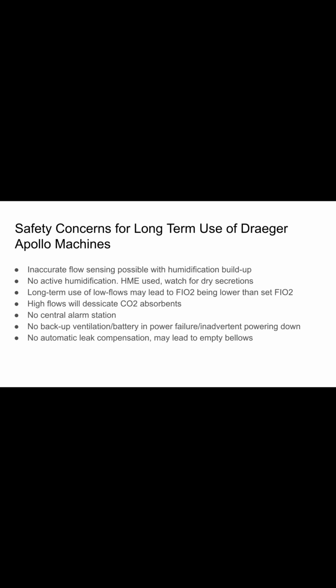So now that you've seen the basic setup for our machines, I want to talk a little bit about the safety concerns for using these anesthesia machines as ICU ventilators. Problems we anticipate have to do with humidification buildup inside the machine itself. Because these are going to be used for longer periods of time, the likelihood is that we will see water buildup in the components, and that could lead to inaccurate flow sensing. We're going to be doing machine checks every 3 days to try and prevent this and detect it before it happens, but be aware that this is definitely a possibility.